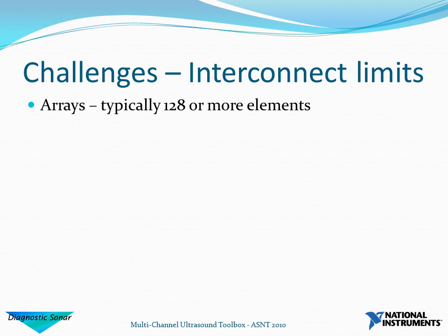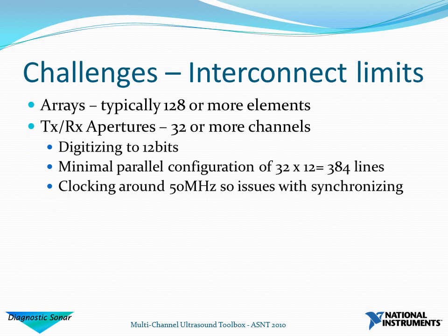We also have a challenge with the number of interconnect lines. Our step-scan array typically has 128 or more elements, but it's more relevant to consider the active aperture at a time. If we've got a transmit-receive aperture of 32 elements with 12-bit digitizing at 50 MHz, that involves 32 times 12, which is 384 separate tracks if you're acquiring in parallel. This is a real challenge at those data rates, so we need to find some alternative.